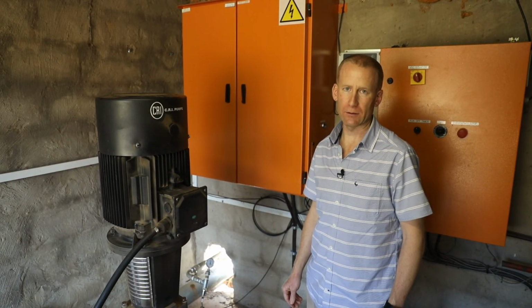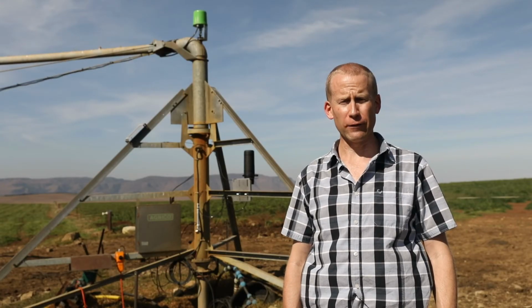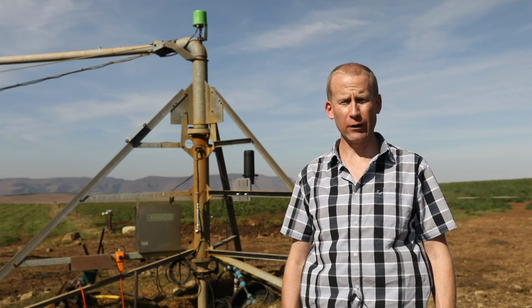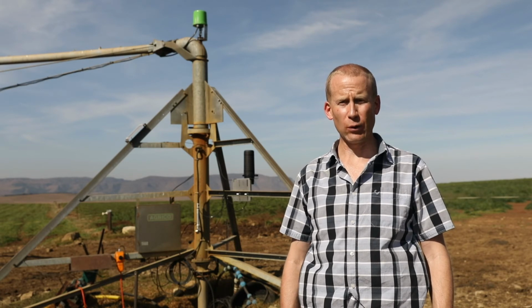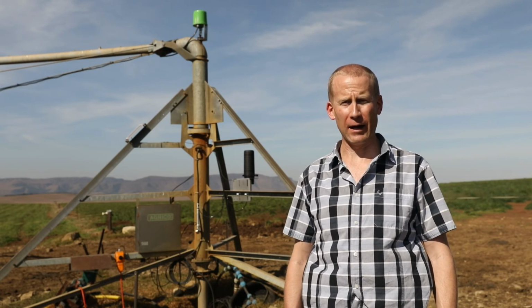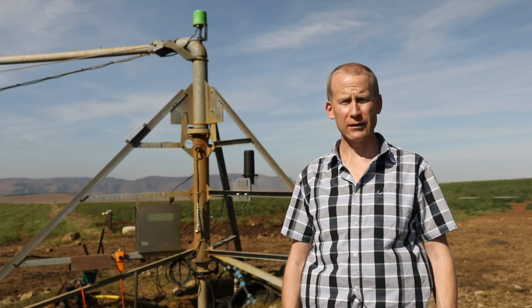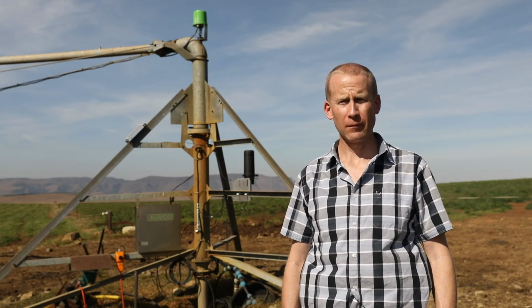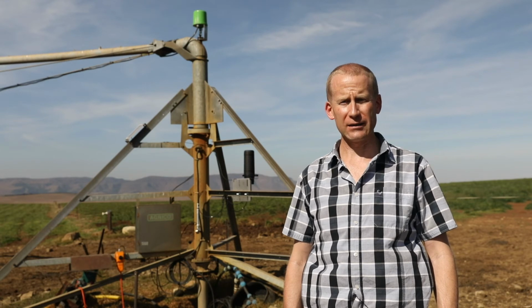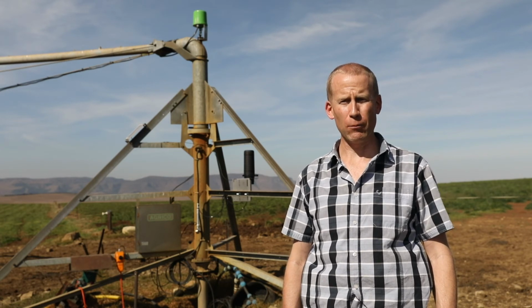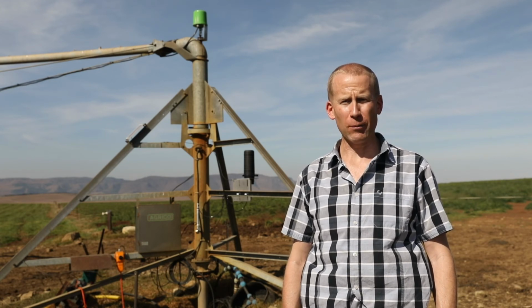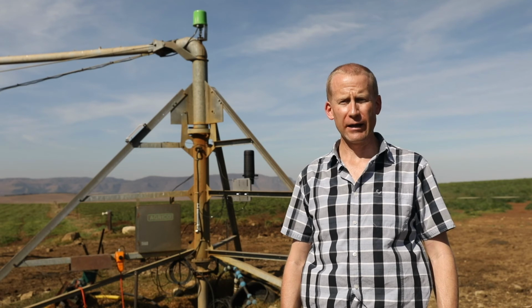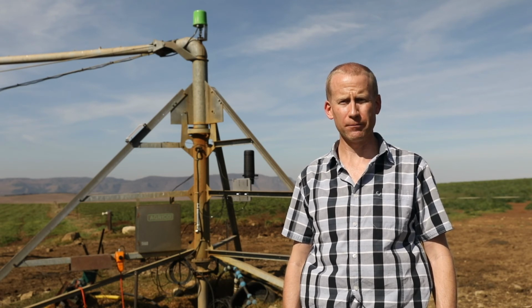pivot being 80 meters. I'm standing at the center of Hlogoma pivot belonging to Murray Turner outside Underberg in KwaZulu-Natal. Shockwave Engineering tested this pivot as well as a supply pump and pipeline. Initially, the power consumption was 40 kilowatts. Shockwave Engineering analyzed the data and found that the pump was incorrectly sized for the flow rate, the pump was worn, and the pipeline was far too small. There was also excessive pivot pressure.